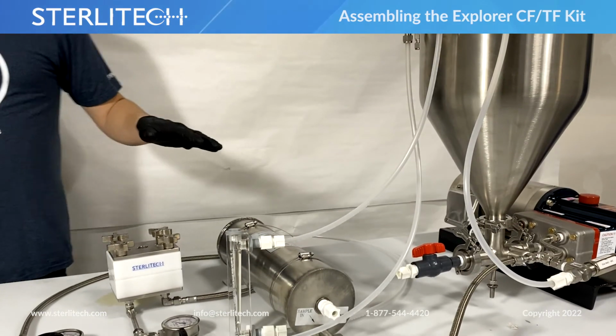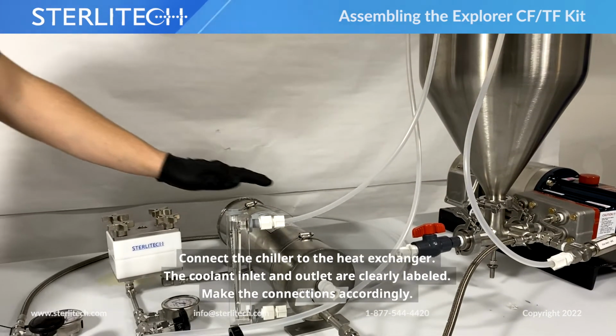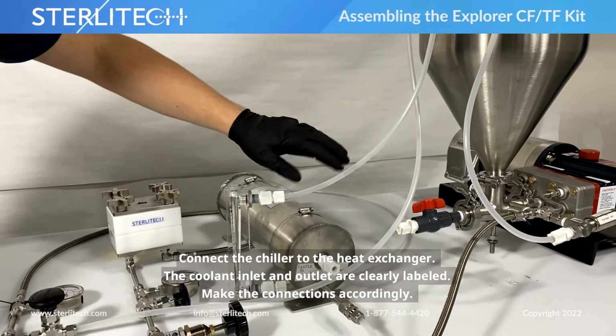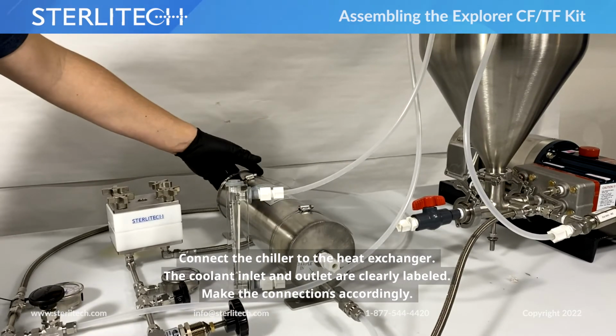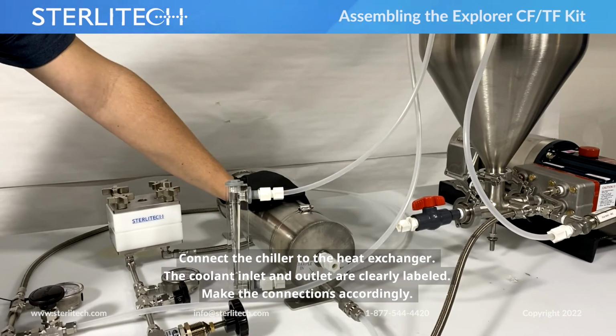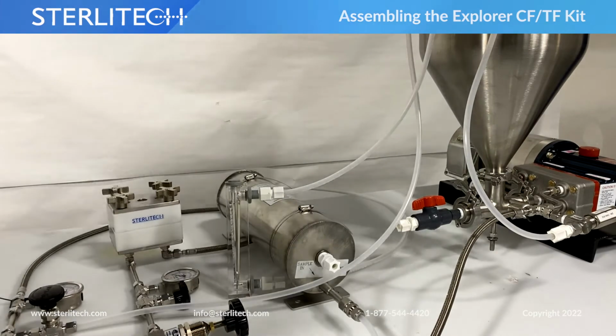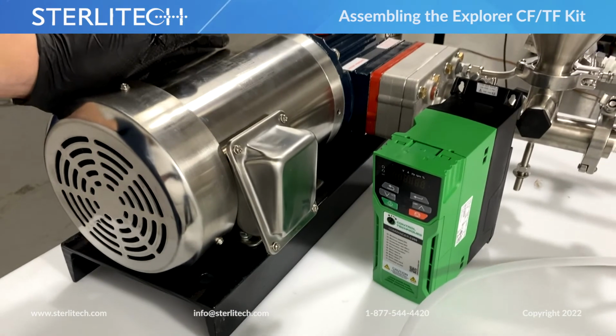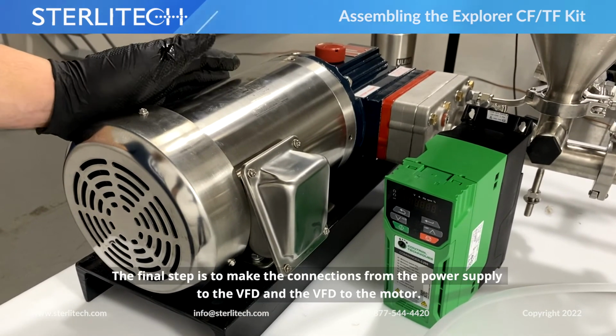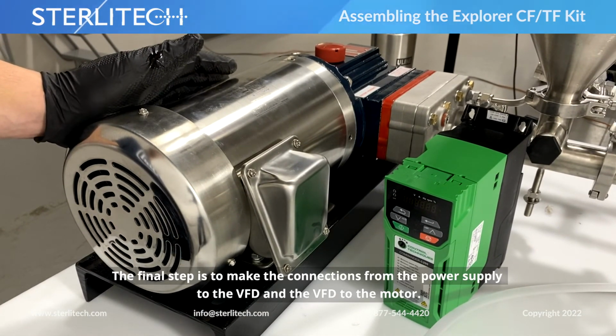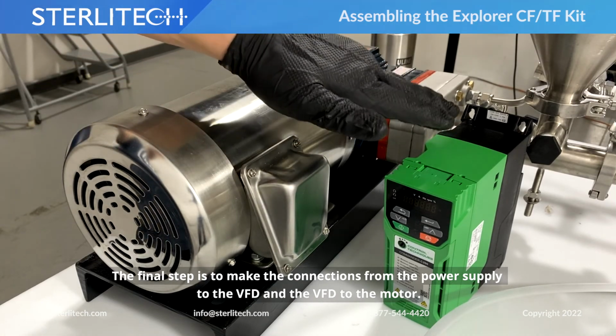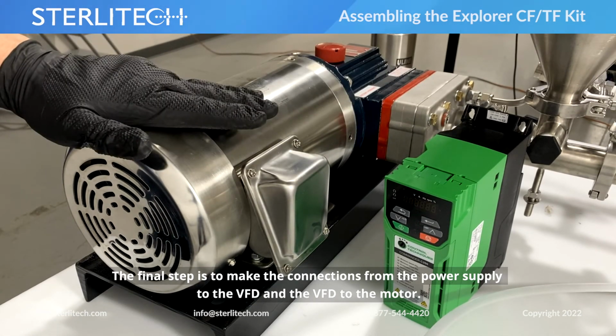From here, all that's left to do is we're going to need to connect our chiller to our heat exchanger. It's got the coolant inlet and outlet clearly labeled, so just hook up your chiller appropriately. Next, let's go over VFD and power requirements. Okay, so the final step is going to be making the connections from our power supply to our VFD and our VFD to our motor here.